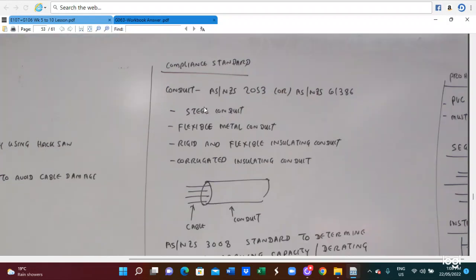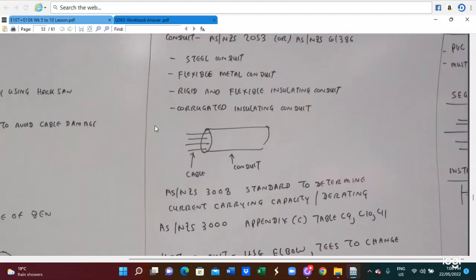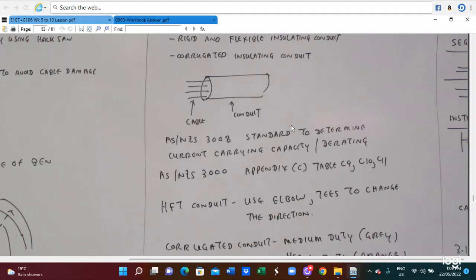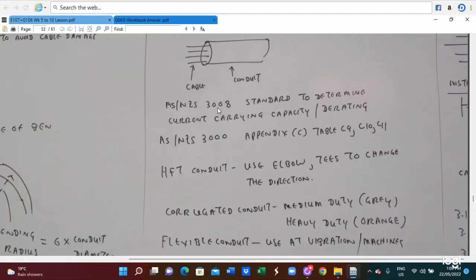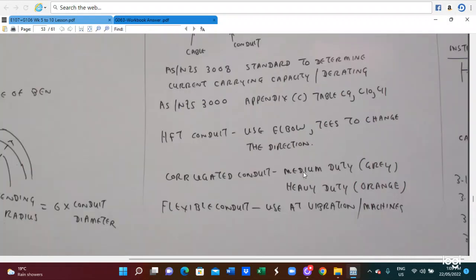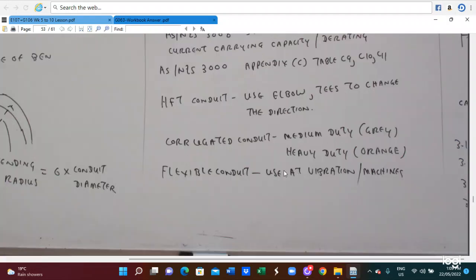And for the compliance standard, we have to follow the AS/NZS 2053 or the AS/NZS 61386. We use steel conduit, flexible metal conduit, rigid and flexible insulation conduit, and the corrugated insulating conduit are utilized. So this is the cable and the conduit. AS 3008 is the standard to determine the current carrying capacity and derating. AS 3000, Appendix C, tables C9, C10, and the HFT conduit, where you use the elbow T to change the direction. Corrugated conduit, medium duty gray, heavy duty orange. Flexible conduit, we use for vibration and machine. This is for the loading.